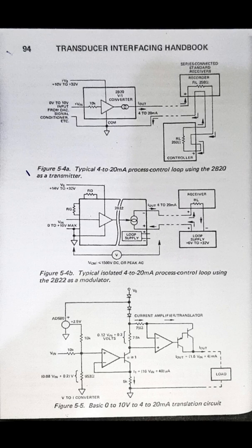No local source of power is needed for the transducer, and only two wires are needed for the transmission. Finally, information in the form of current permits several loads at different locations to be connected in series up to the specified maximum voltage. The output of the transducer could drive a chart recorder and a meter, and provide an input to a controller.